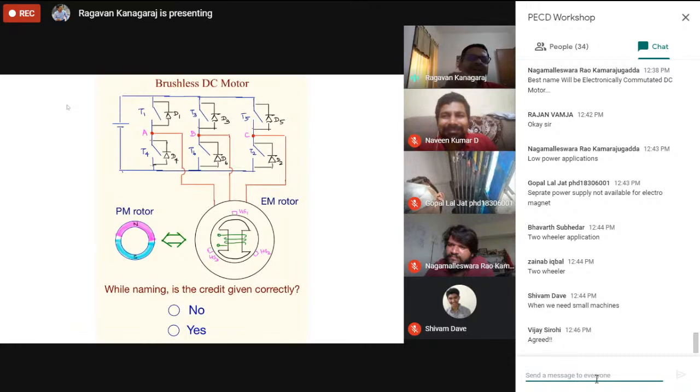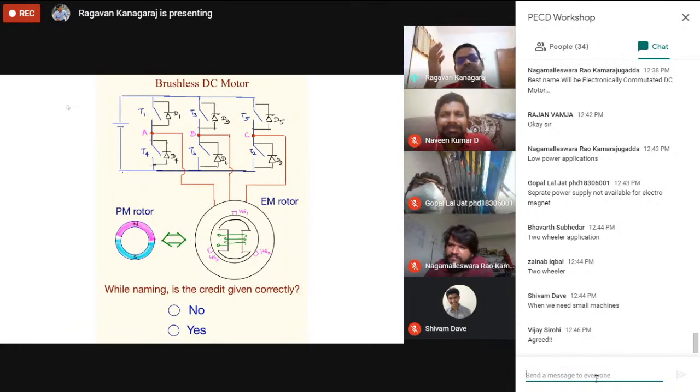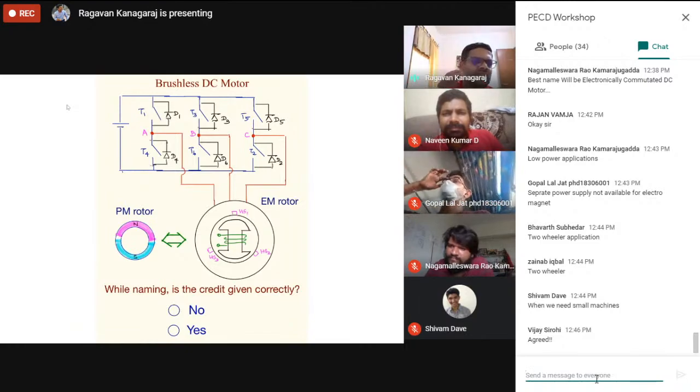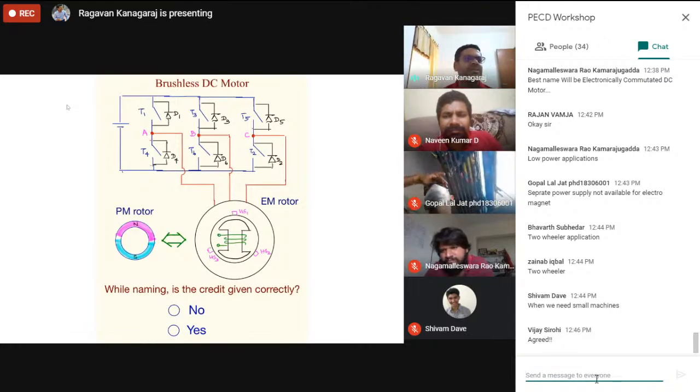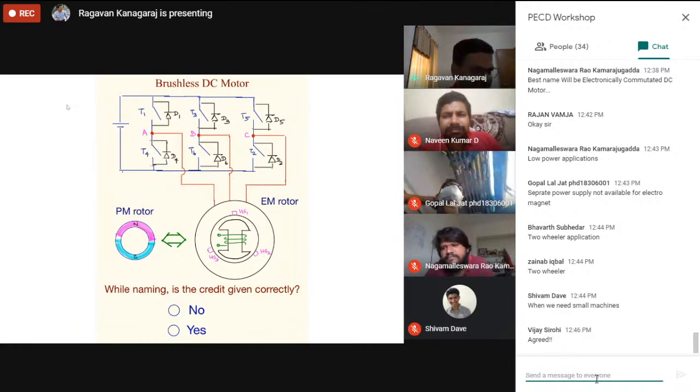All right. And one more great advantage of eliminating permanent magnet is, permanent magnet, initially it's fine, but with time, when the steady state temperature inside the machine keeps on increasing, the thermal shock is there, with the time the property of permanent magnet degrades. Okay, and whenever there is a short circuit problem, then the windings will carry huge current. When the windings carry more current, it produces more magnetic field. Now that magnetic field is going to oppose the magnetic field that's coming out of the magnet, so there is a high possibility of demagnetization.